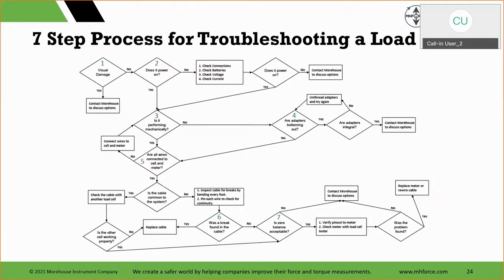Load cell, meter, what's bad? Something's not working. Well, let's put another load cell on the meter with the same cable. Okay, still not working. Two load cells, the chance of two load cells being bad is less. So now we're down to cable or meter. By deduction, you can do that. I just like pinning the meter or pinning the cable from the start to make sure things are good. But, whatever. A lot of times things are simple repairs, such as replacing the cable.